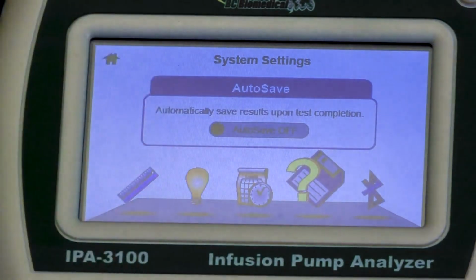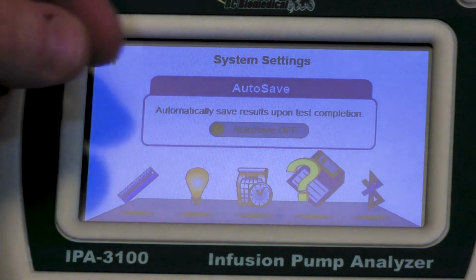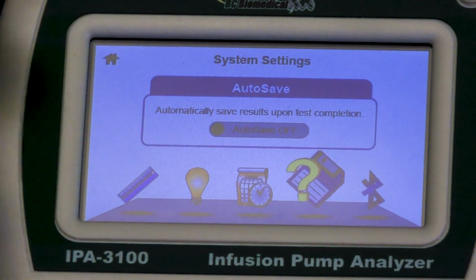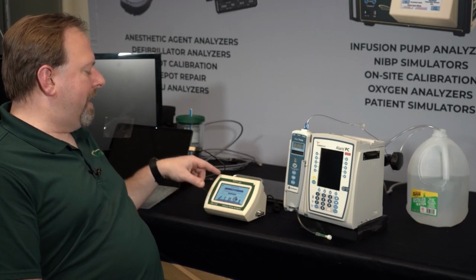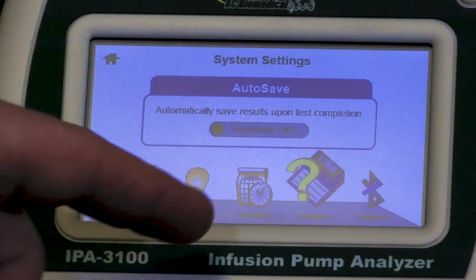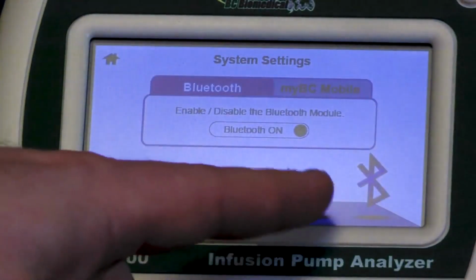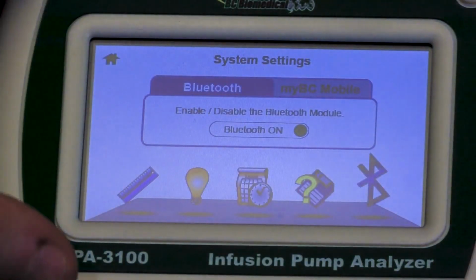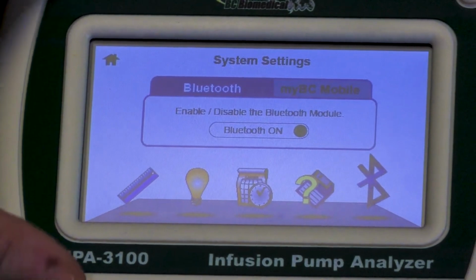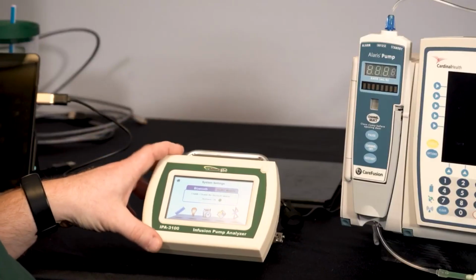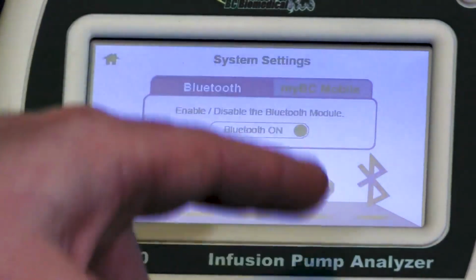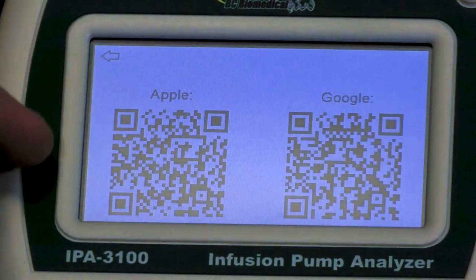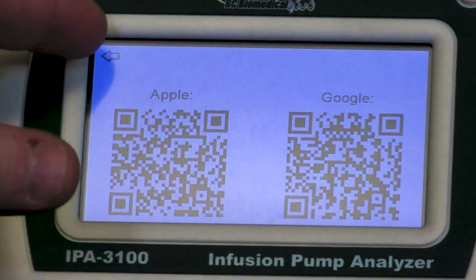The save icon allows us to turn on or off autosave. That's the feature that every time we run a test, at the end of the test, if autosave is turned on, it will save that test record to the database. Or we can turn that off to manually save tests as we run them. Bluetooth, we can turn that on or off. Bluetooth is built in on this unit, and we can turn that off if we want to conserve battery life, or we can leave it on here in this setting. We also have a link directly to myBC Mobile for either Apple or Google devices.